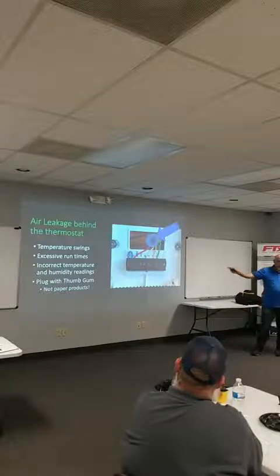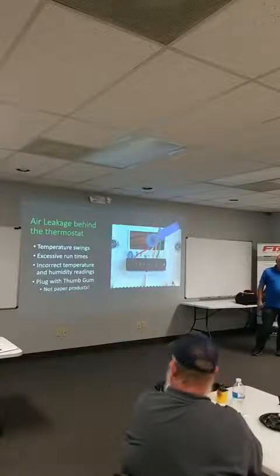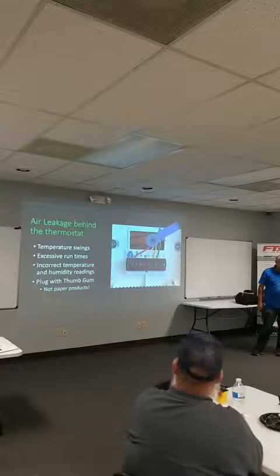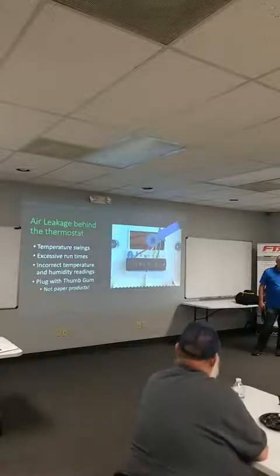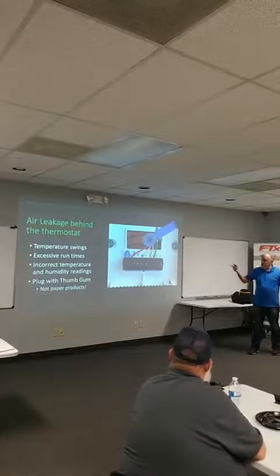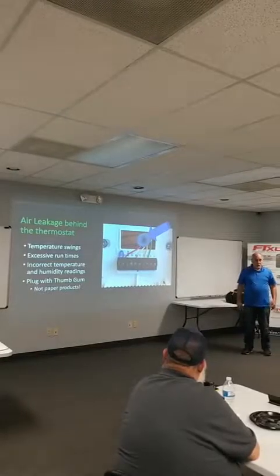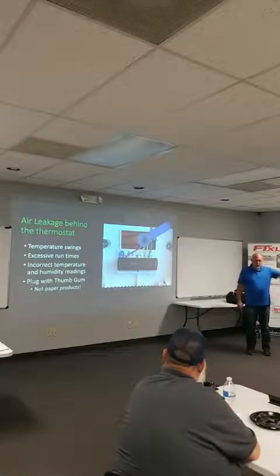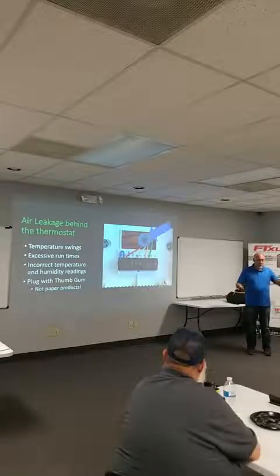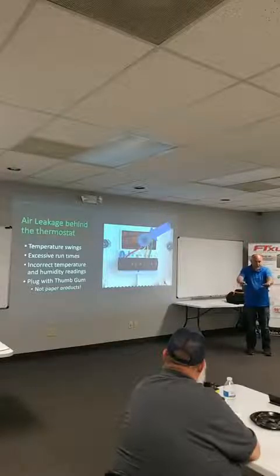Just recently, I had a guy call me about an inverter system. He's saying, I'm having all kinds of problems with humidity control, it's just ridiculous. I'm like, you need to make sure you plug it behind your thermostat, because the wall is an unconditioned space. And he had it communicating with a crawl space. Not only is it a crawl space, it is an unencapsulated crawl space, meaning there's no plastic, it's a dirt floor underneath.